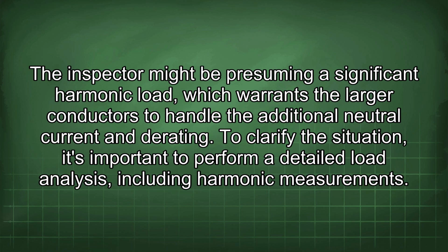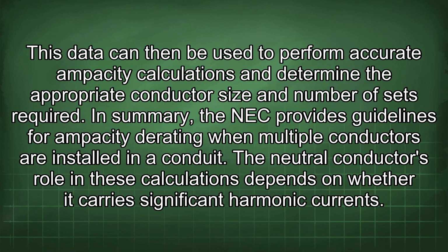The inspector might be presuming a significant harmonic load, which warrants the larger conductors to handle the additional neutral current and derating. To clarify the situation, it's important to perform a detailed load analysis, including harmonic measurements. This data can then be used to perform accurate ampacity calculations and determine the appropriate conductor size and number of sets required. In summary, the NEC provides guidelines for ampacity derating when multiple conductors are installed in a conduit.